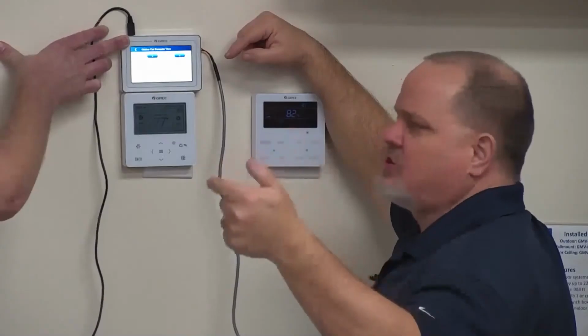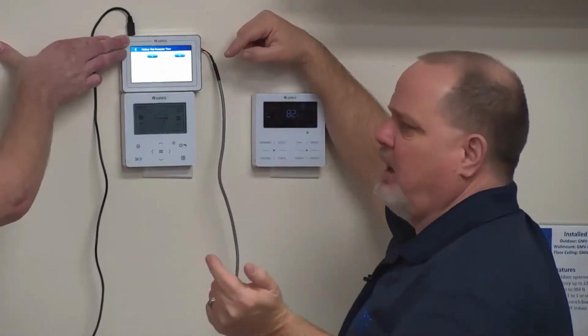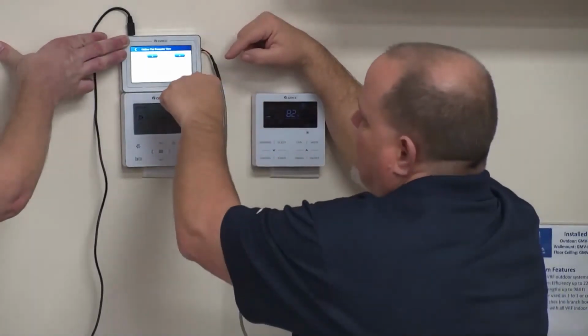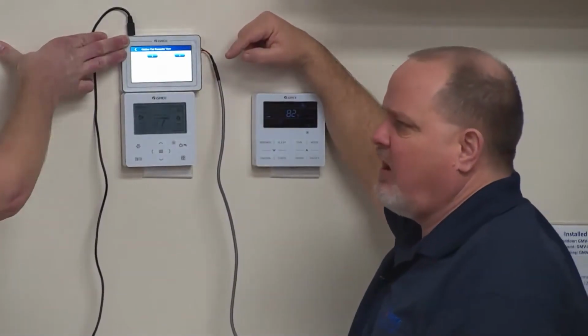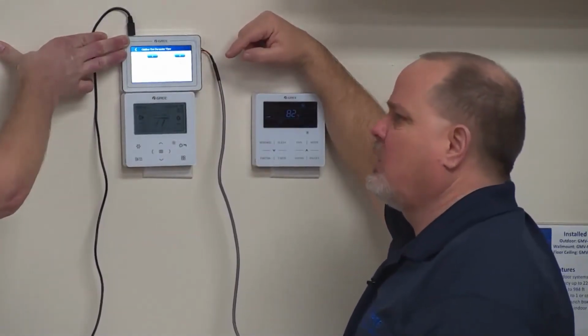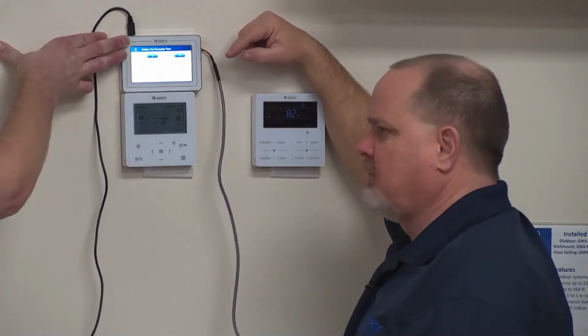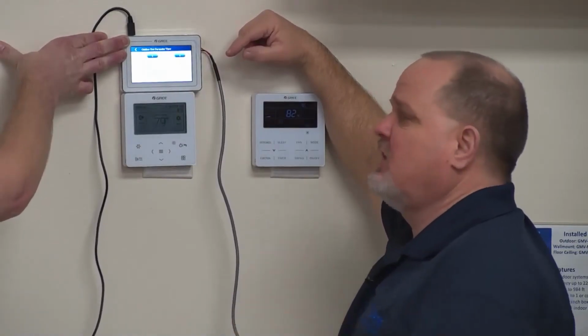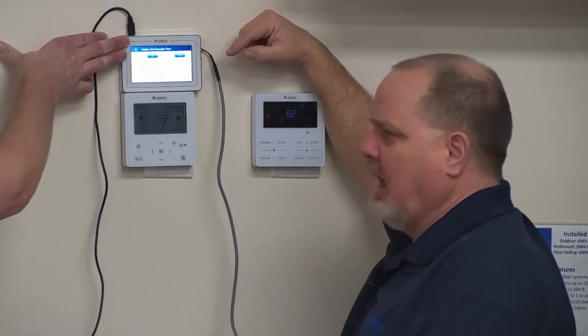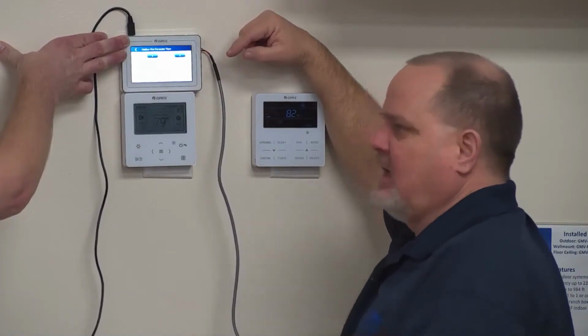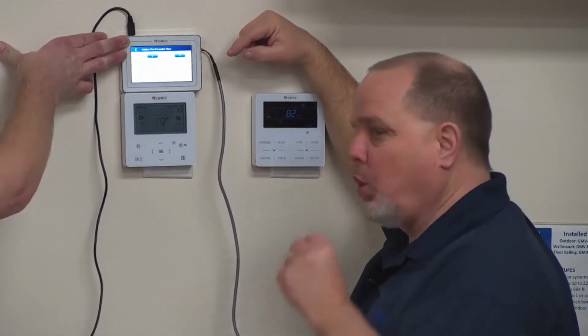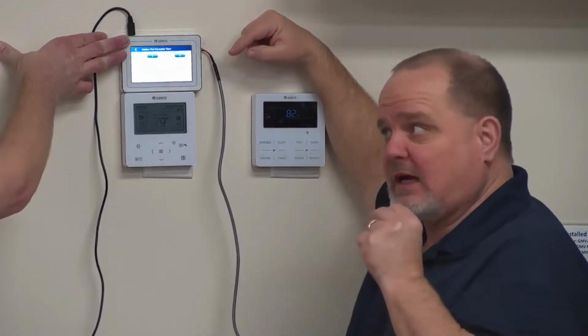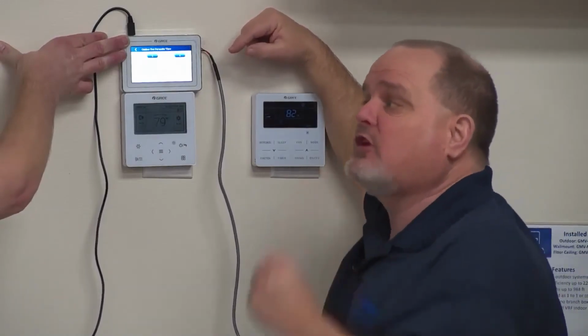All the way up to around 150 degree discharge temperature, or maybe even just a touch higher, I'm not alarmed by that. But if I start seeing that discharge temperature at 175 plus, I'm beginning to wonder why I'm not getting enough refrigerant back to my compressor. If I start seeing it over 200, I know I've got a problem. I'm not getting my refrigerant back to that compressor, or I am overheating because of lack of refrigerant.